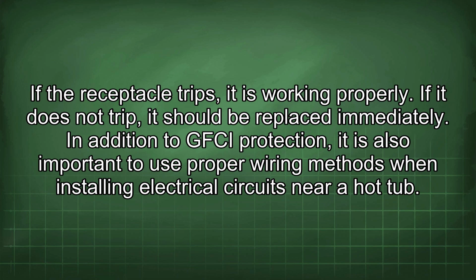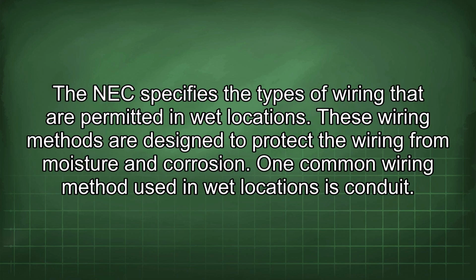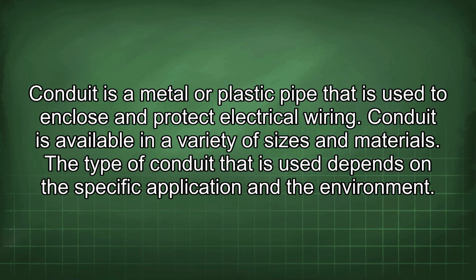In addition to GFCI protection, it is also important to use proper wiring methods when installing electrical circuits near a hot tub. The NEC specifies the types of wiring that are permitted in wet locations. These wiring methods are designed to protect the wiring from moisture and corrosion. One common wiring method used in wet locations is conduit. Conduit is a metal or plastic pipe that is used to enclose and protect electrical wiring. Conduit is available in a variety of sizes and materials. The type of conduit that is used depends on the specific application and the environment.